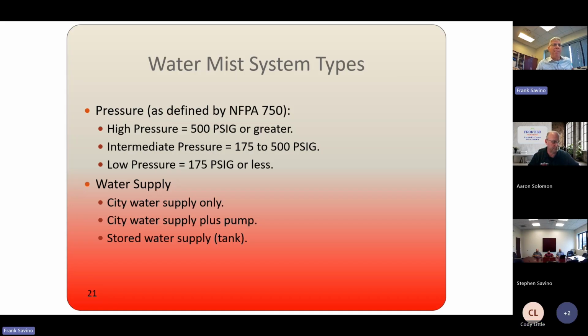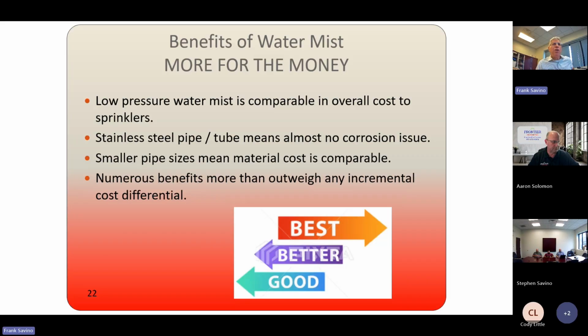And you'll see what I mean by that in a minute. Okay, so with water mist, you really get more for the money. Low pressure water mist is comparable in overall cost to sprinklers. Stainless steel pipe and tubing means you really don't have much of a corrosion issue like you have with carbon steel pipe. Smaller pipe means lower material costs. The stainless is more expensive than carbon steel, but the lower sizes offset that. And I believe that the numerous benefits, especially for a large data center application, outweigh any incremental cost differential.